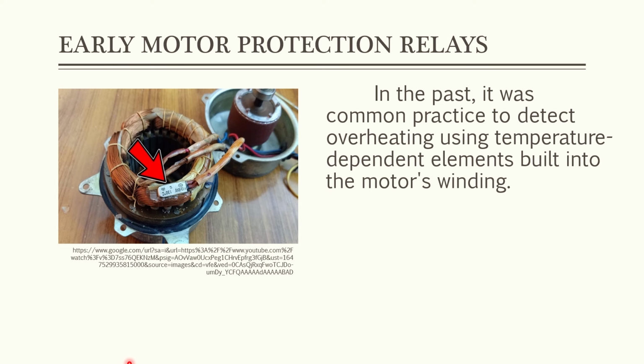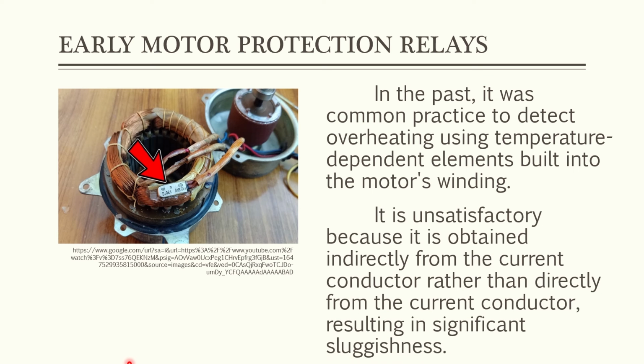is that in the past, it was common practice to detect overheating using temperature-dependent elements built into the motor's winding. So we can see in the picture that our temperature-dependent element is attached to the stator winding, to the coil. But the other side, the negative side of it, is that it is unsatisfactory because the measurement is obtained indirectly from the current conductor rather than directly from the current conductor, resulting in significant sluggishness. So our temperature sensor is not attached directly to the current-carrying conductor, and it is attached only to the insulation. So there is a difference in the result of the temperature sensor when we attach it on the insulator compared to when we attach it directly on the current-carrying conductor.